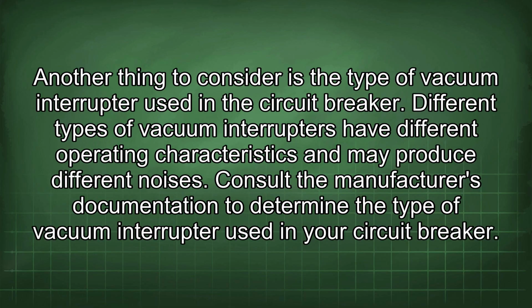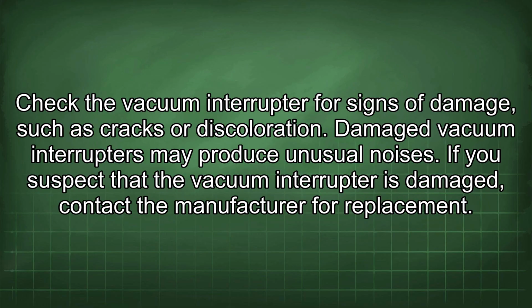Another thing to consider is the type of vacuum interrupter used in the circuit breaker. Different types of vacuum interrupters have different operating characteristics and may produce different noises. Consult the manufacturer's documentation to determine the type of vacuum interrupter used in your circuit breaker. Check the vacuum interrupter for signs of damage, such as cracks or discoloration. Damaged vacuum interrupters may produce unusual noises. If you suspect that the vacuum interrupter is damaged, contact the manufacturer for replacement.